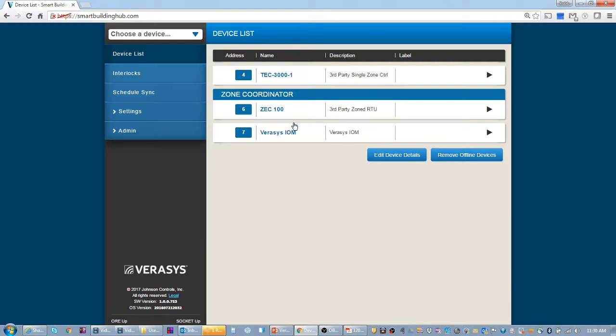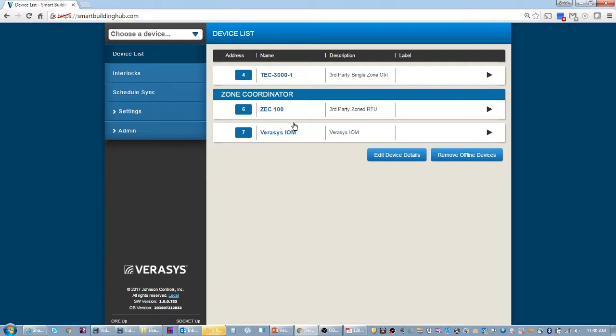The reason why I like to do it this way is so that I can focus on major pieces of equipment at one time. If I can get my zone coordinator talking to my rooftop unit, I then have the ability to start to send cold air or warm air down the duct and temper the space. Then once I have the cold air going down the duct, I can go to each device and set them up individually.